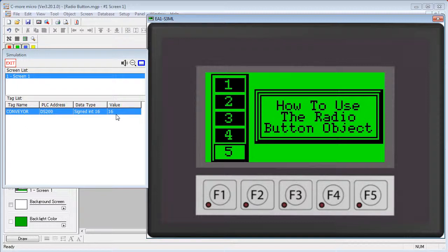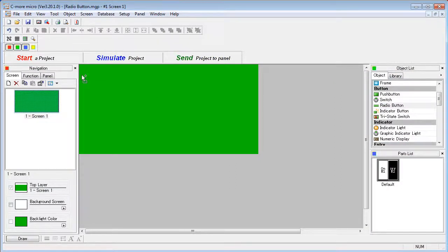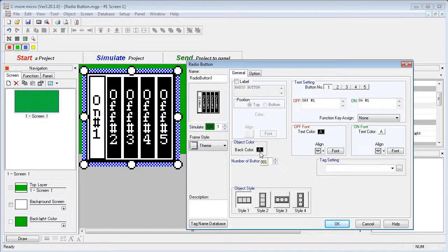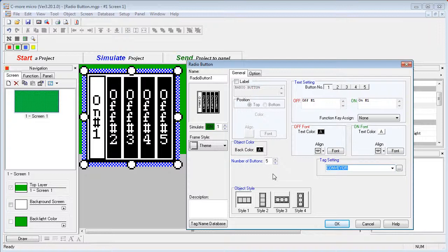Let's do an example and see how to set this up. Double click or drag the radio button onto the screen. Just pick the number of buttons you want — we'll use 5 here. Specify the tag that the switch will modify; we'll use the conveyor tag in this example. See the 'how to use common object features' video for all the formatting options — we are not going to mess with that here. On this radio button object you can set the on and off text for each individual button. Just choose the button to modify right here.